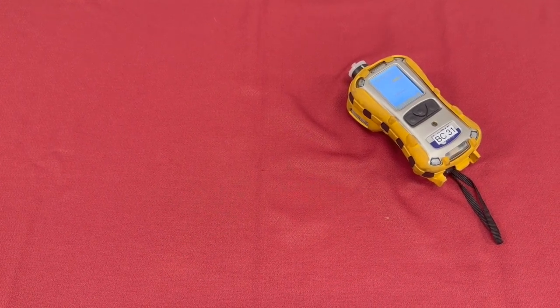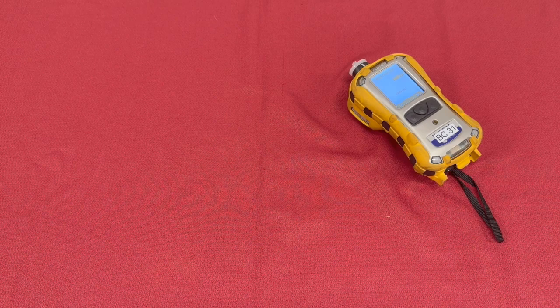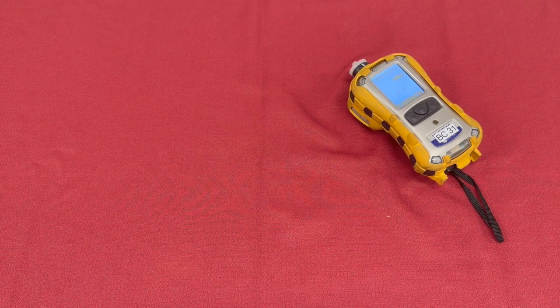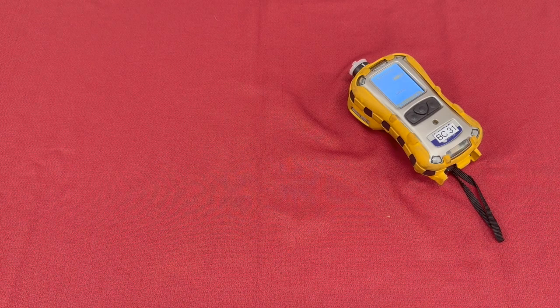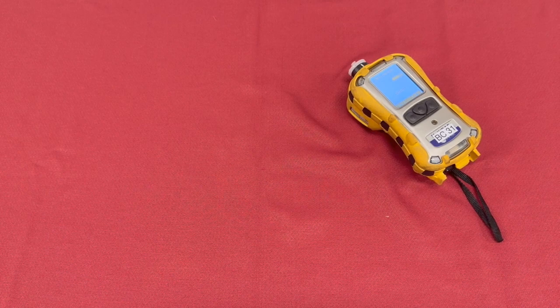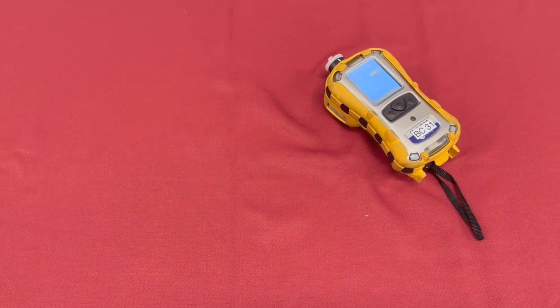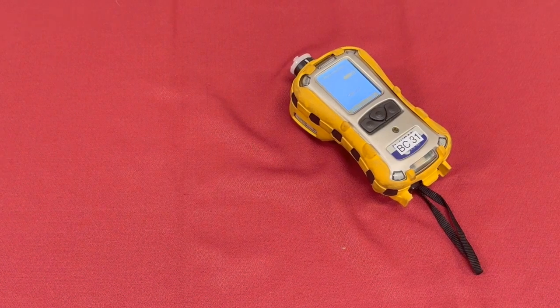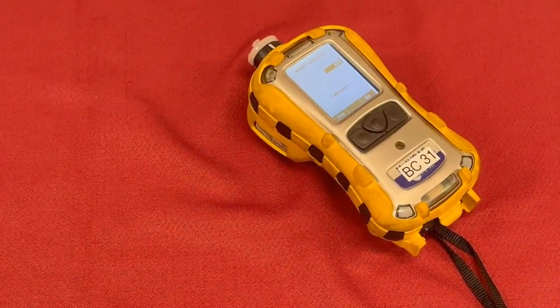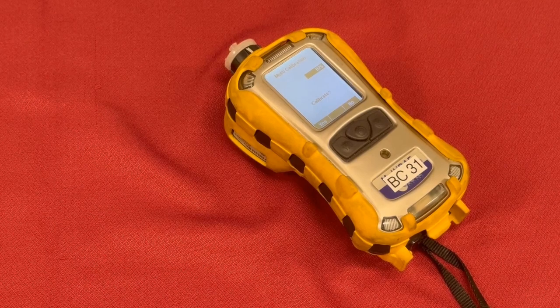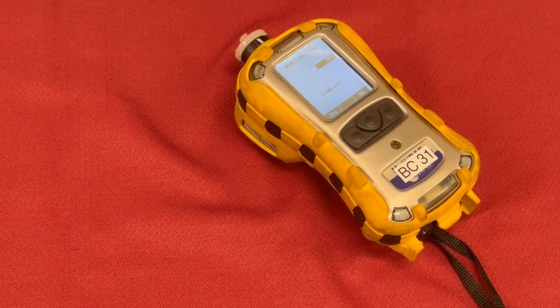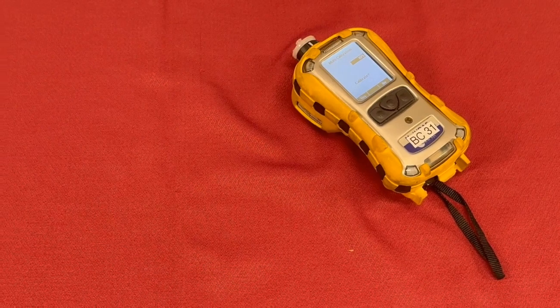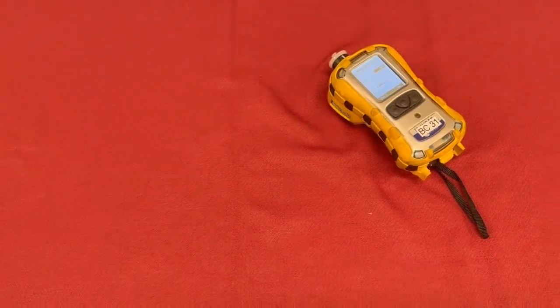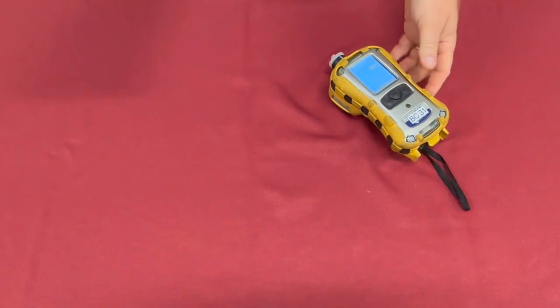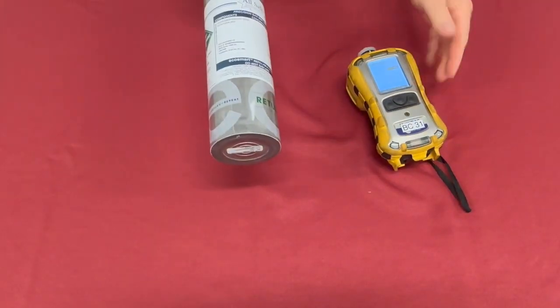One of the things we want to do during this time is give the meter a few moments to run on this fresh air and just kind of get itself balanced back out. We just flooded the meter with a bunch of different gases, and if we do this calibration or bump test, either one, as fast as you can do it, what's liable to happen is you got some cross sensitivities on these sensors and you'll fail one of them. It's no harm to let it sit here and run for just a minute before we move on to the next product. The next thing the meter has been programmed to ask for is H2S, which is hydrogen sulfide.